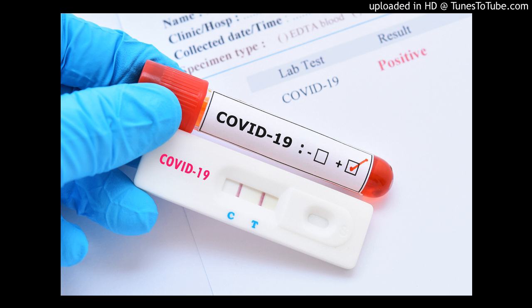So maybe this is a 3 gene kit. It's very good for us and we trust it. We think we can work with it. And others will also look at it in terms of the platform. Do you have the platform that this kit has been validated on? That is very important. Some of these manufacturers make the test kit and say they validated it, for example, on the ABI, the Applied Biosystems. Others will say it is validated on the Roche, the Roche LightCycler PCR machine. So you need to look at what you have and what the kit was originally validated on.